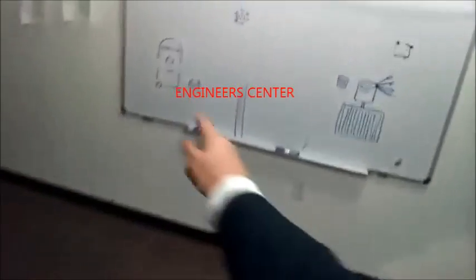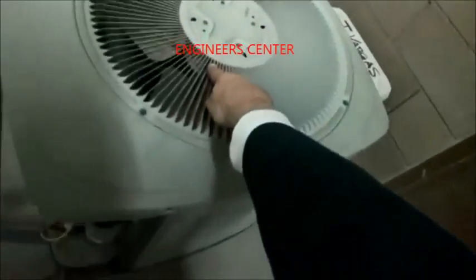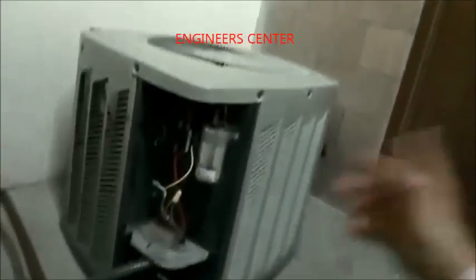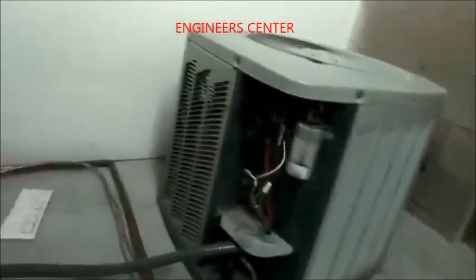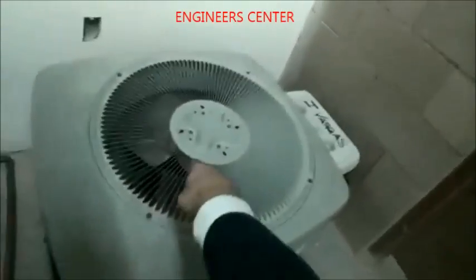And so outside of that, we have other parts that are very important. We have compressors, and I know I don't have to show you guys what those look like. Oh, we have motors. Well, let me go out here, show you guys. So you have your motor, and you have your compressor in there. And you have a capacitor. Outside of that, there's nothing else to it. Contactor, compressor, condenser motor. And in here you've got the blower motor, of course. So we're talking about air conditioning right now, and so I'm not going to go into heating too much. But here we are.